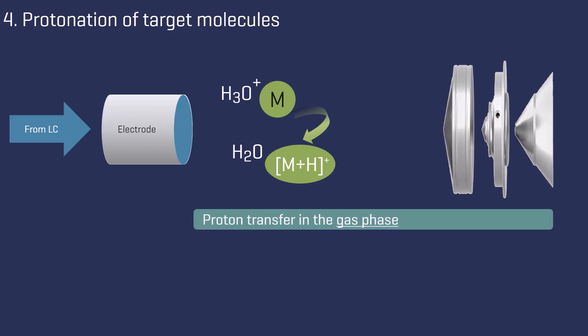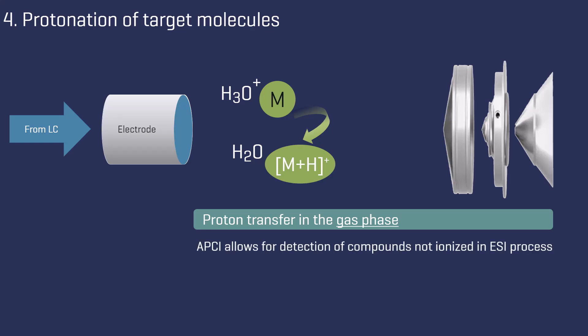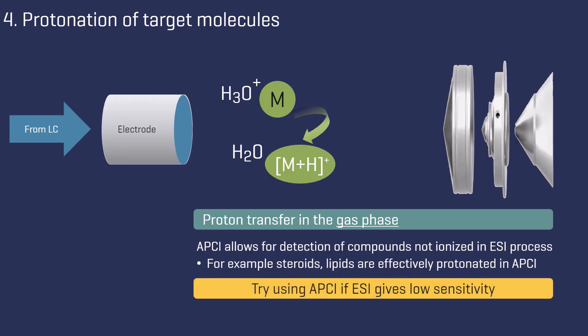This process occurs in the gas phase. Unlike electrospray ionization, where it takes place in the liquid phase, gas phase proton transfer allows for the detection of compounds that do not easily ionize in liquid, such as steroids and lipids, which are effectively protonated in APCI. So try using APCI if ESI gives low sensitivity.